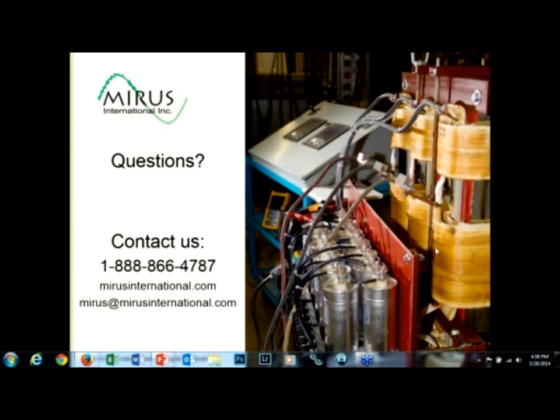The filters can be applied to multiple loads. They can be used on a single VFD load, or you can combine VFDs and size the filter appropriately for multiple VFDs. It is not presently available for medium voltage. The main reason for this is that you need to combine this filter with a 6-pulse drive in order to get the performance that we require, the reduction in harmonics. And there are no drive manufacturers today that provide a 6-pulse medium voltage drive, because they know that the harmonic content of a 6-pulse drive would create too many problems. And with a medium voltage drive, they're typically quite large drive systems, so they put some form of treatment, be it multi-pulse with phase shifting, an active filter, or some other form.